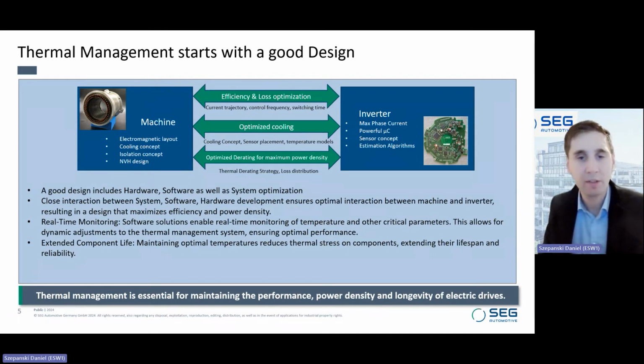The third point is an optimized derating strategy. That means how we handle situations where the maximum temperature is being reached. Good real-time monitoring is needed to go as close as possible to the boundary conditions. Therefore, the thermal model that captures temperature must be as precise as possible.